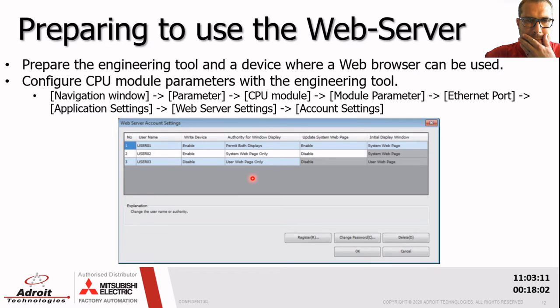A nice thing is you can also enable write access to the devices. So if you want to change a set point from the web service, you can do it. If you don't want somebody to do it, you can disable it. Once disabled, that person can't change any settings, he can't start a motor by accident, or lower set points for a PID loop, for example.